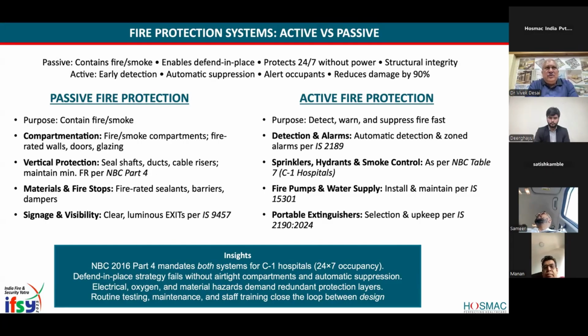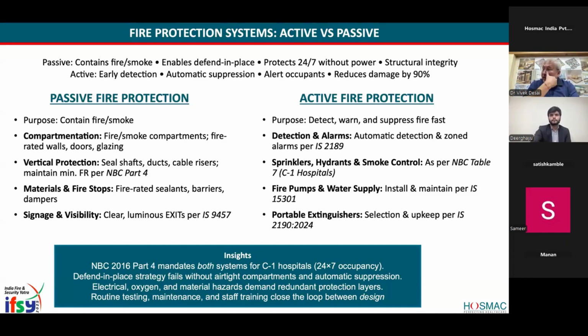So you have to seal the shaft so that fire doesn't travel, as he was saying in terms of dampers in air handling units. Then the cable risers, because electrical wires also will carry the fire, all those should be maintained as per NBC Part 4, National Building Code. Materials and fire stops, fire rated sealants, barriers, dampers, signage and visibility. This is one of the problems, that you may not know where to run in case of fire. So it should have luminous exit signs on the floors.